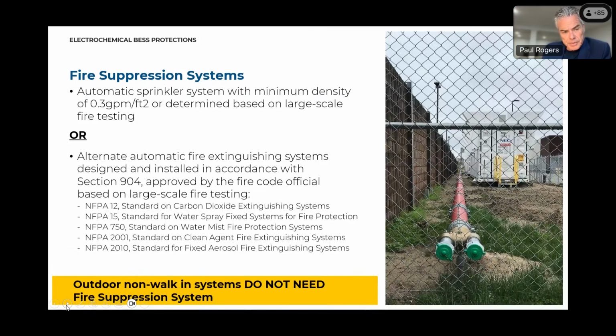Fire suppression systems. Automatic fire suppression for indoor installations. If you could take a look at this one, this is a little different here, right? I'm sure people are saying, wait a second, there's a fire suppression system and that's an outdoor system. That's a cabinet outdoors. No, that's not a cabinet. That's an indoor, that's technically a walk-in container. As you remember what I said before, walk-in containers are considered to be like a building. So they do need to have a suppression system on the interior of the box itself.